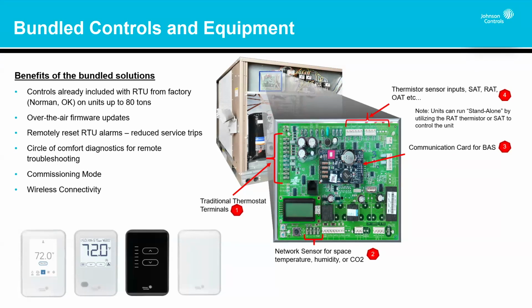We also now have a commissioning mode dedicated to Verasys—one-click commissioning. It requires that all the rest of the equipment connected to that system, rooftop unit, VAV boxes, changeover bypass, damper controllers, bypass controllers, whatever it is, be fully programmed and functional. We've combined test and balance with calibration of zone controllers and rooftop units into one exercise, which dramatically reduces time spent commissioning and balancing these systems.